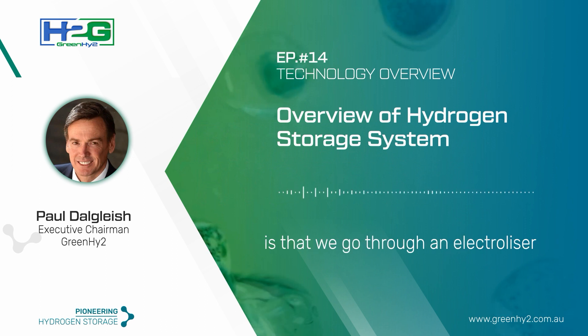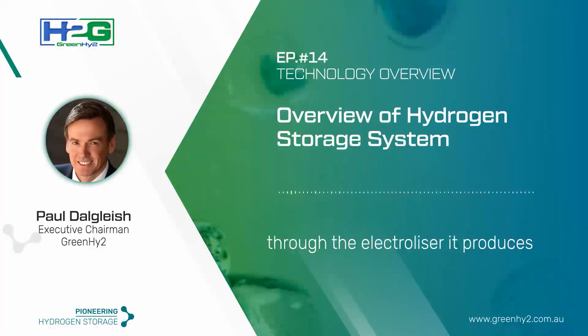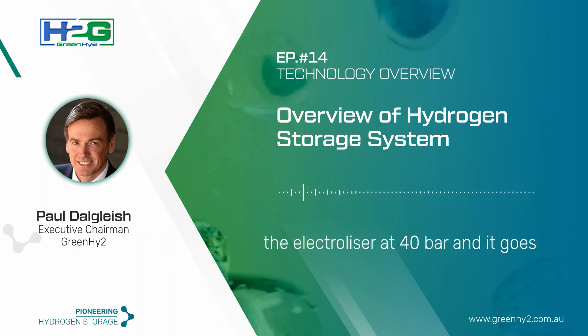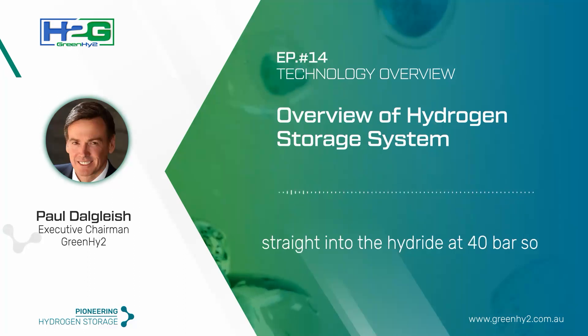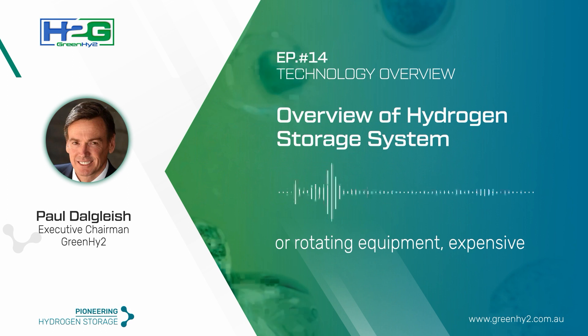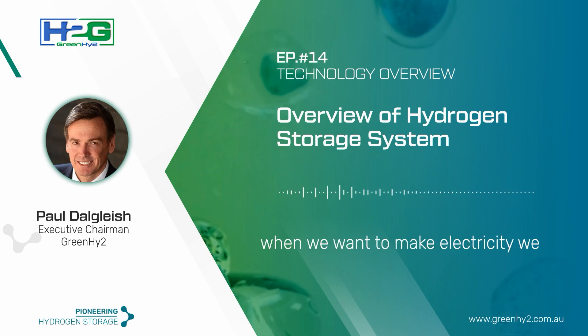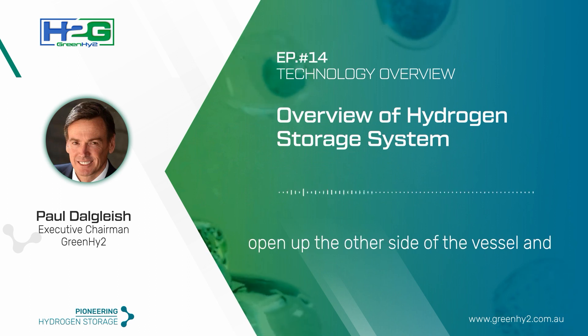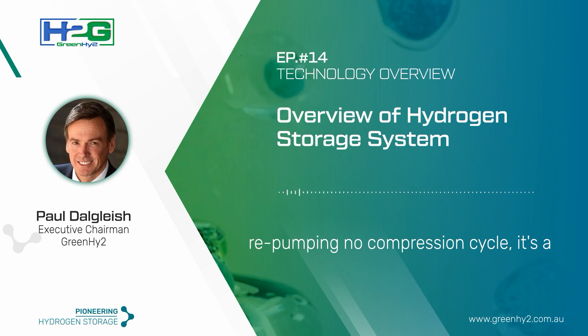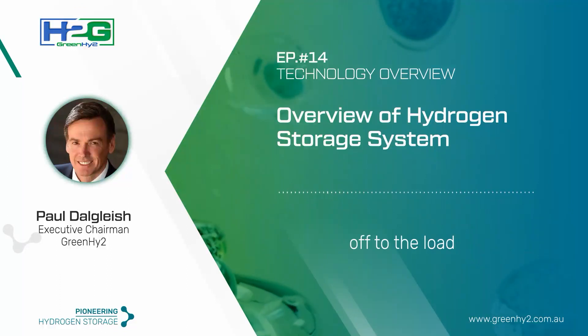How it works is that we go through an electrolyzer from a renewable energy source such as solar, wind, or hydro. The electrolyzer produces hydrogen as a gas; we put that into the metal hydride at 40 bar — straight in with no compression, no pumps, no expensive rotating equipment. It stores as a solid. When we want to make electricity, we open up the other side of the vessel and the gas comes out at two bar and goes straight into the fuel cell — again, no repumping, no compression cycle. It's a straight chemical reaction, and the electricity made then goes off through the fuel cell to the load.